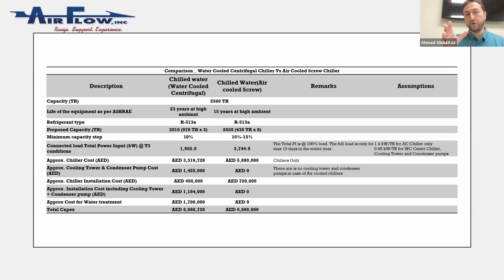This is your chillers only, because for sure you will have AHUs, fan coil units, VAVs, everything will be almost the same inside the building. Now, for air cooled, you have different accessories and items to add. For water cooled, you have other items to add to complete your system. So the approximate cost for the cooling tower and condenser pumps, this is only for water cooled, is 1.4 million dirhams, and 0 for air cooled. Then the installation itself, the labor, the pipes, everything else will cost you 450,000 for water cooled and 720,000 for air cooled. Now, if you sum up all the accessories, you will get 1.1 million dirhams, 0 for the condenser pumps and cooling towers.